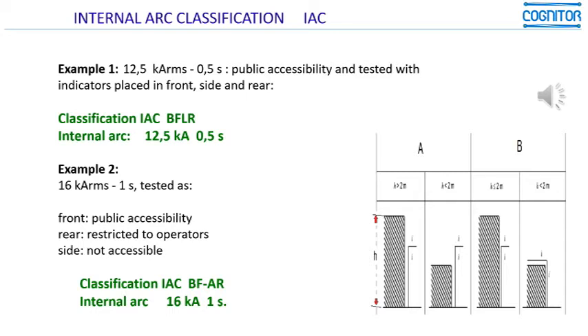Suppose that one equipment was tested with 16 kArms, with a duration of 1 second, and was tested such that the front is accessible by the public. In this case, the access is restricted only to operators and the side is not accessible.